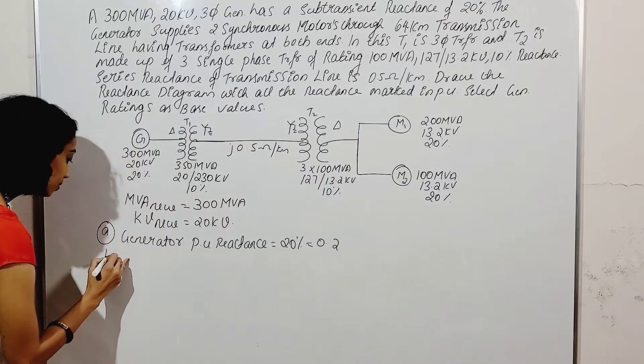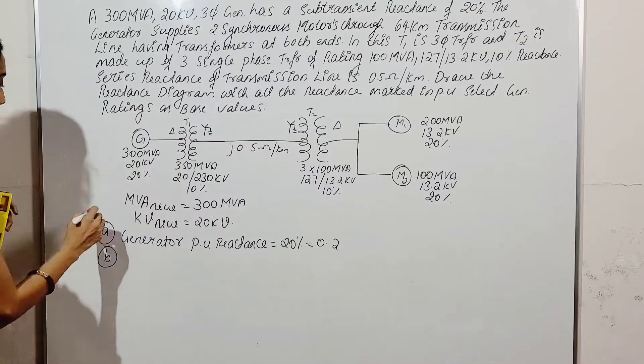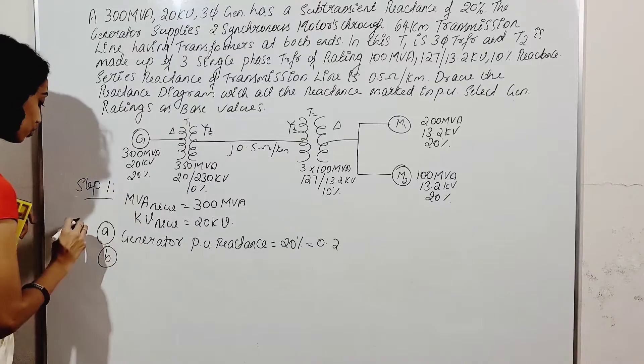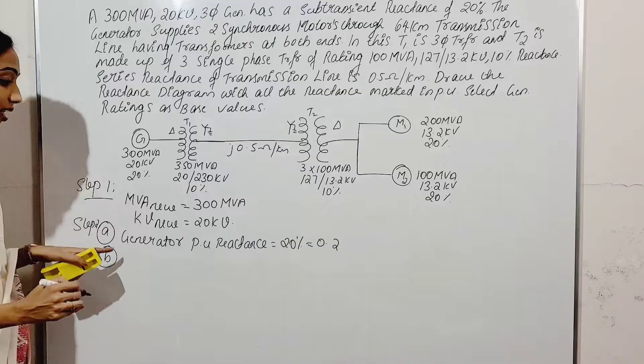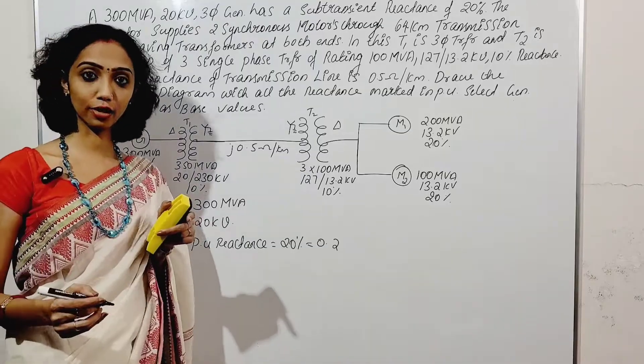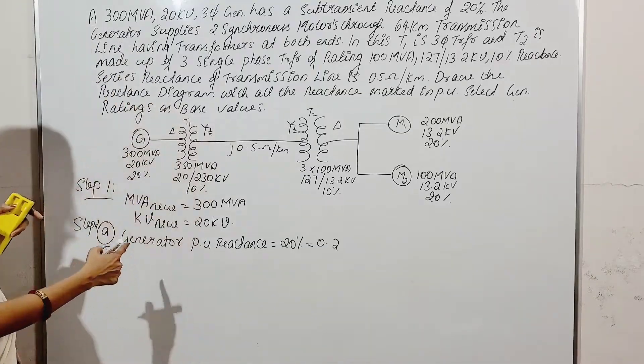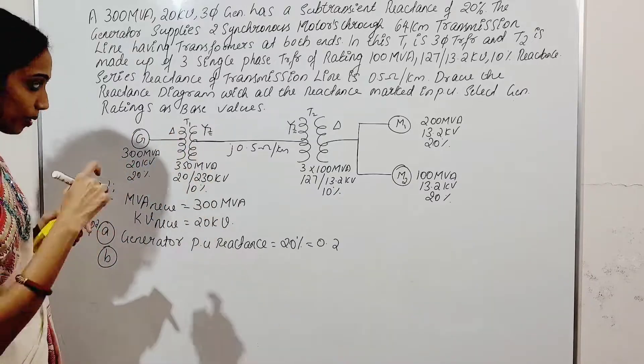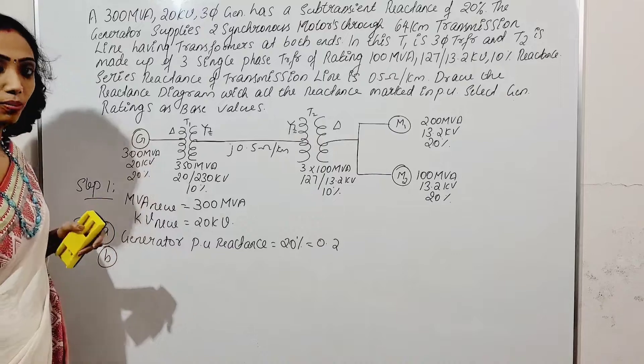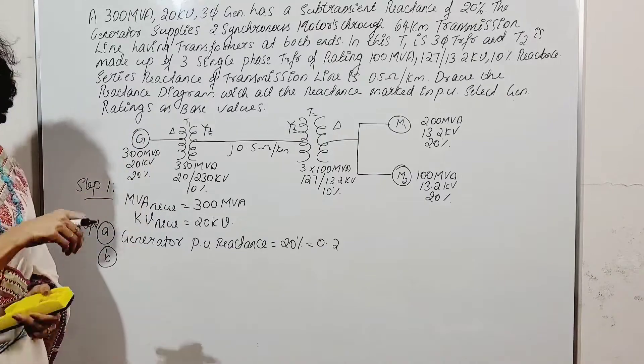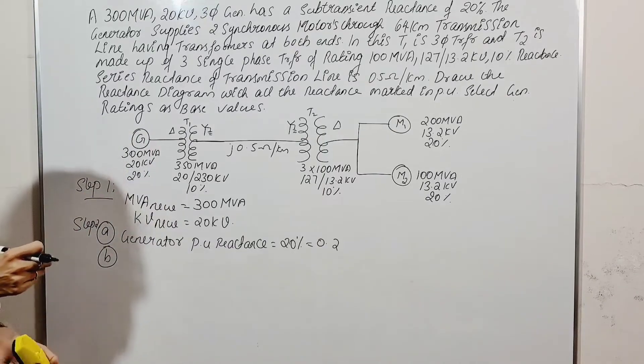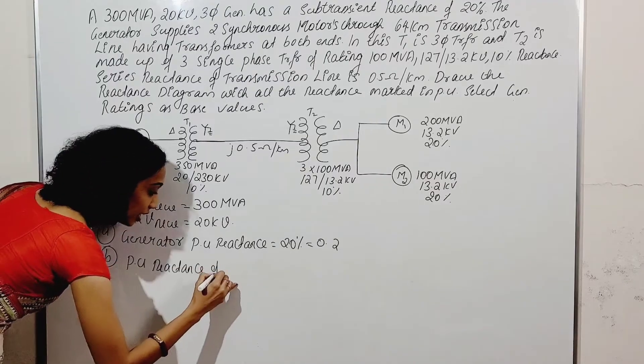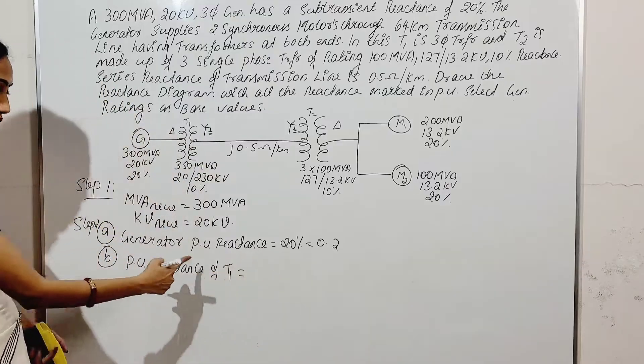Step 1: we choose the base values. Step 2: we choose the per unit reactances. So the per unit reactance of the generator is determined. Then we add transformer T1. For transformer T1 we also choose base values and then calculate the per unit reactance. So per unit reactance of T1 — here you use the formula X_PU new equals X_PU old into (KVB old / KVB new) squared into (MVA new / MVA old).